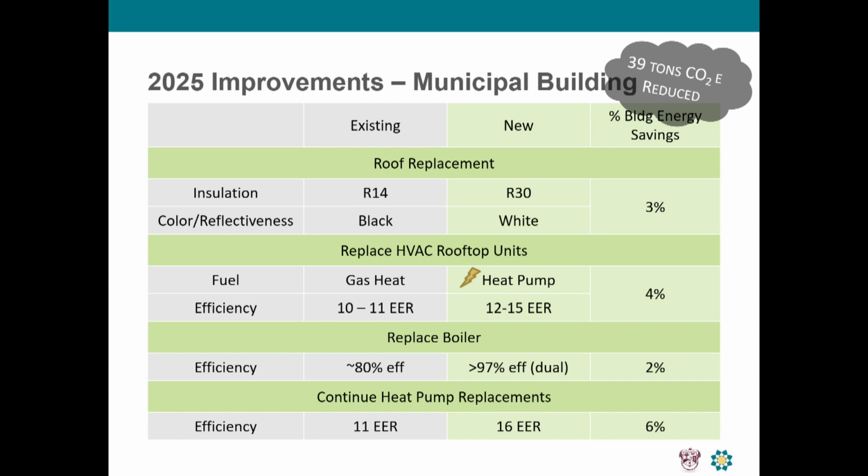The boiler you currently have is more of a conventional boiler. It's really designed to generate really hot water, for that hot water to be the primary heating fluid in the building. With water source heat pumps, it's just providing 70-degree water, maybe 80-degree water that they can just extract heat from. Condensing boilers reach their peak efficiency the lower the water temperature they have to deliver, the higher their efficiency. So it's an ideal application for a condensing boiler, which is great in this situation. The alternative to that, you could do away with the boiler and do away with the cooling tower if you had, for instance, a geothermal well field.